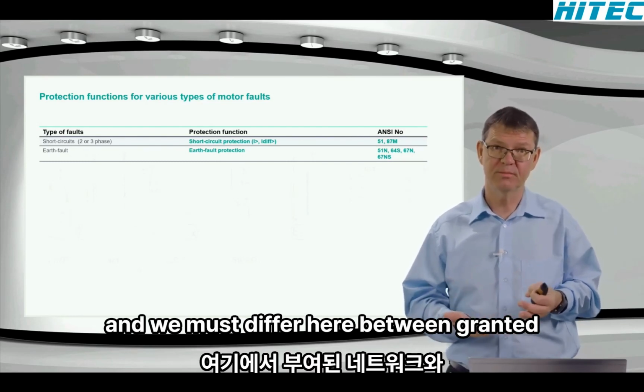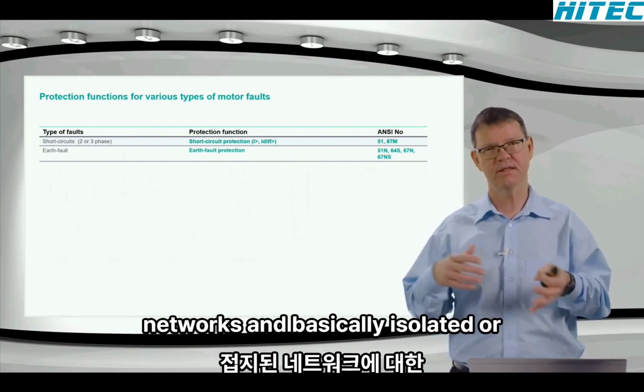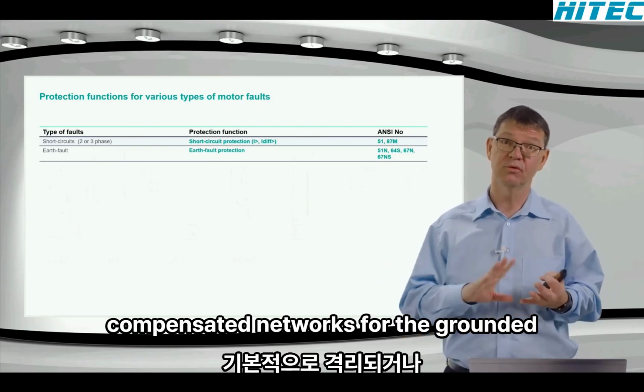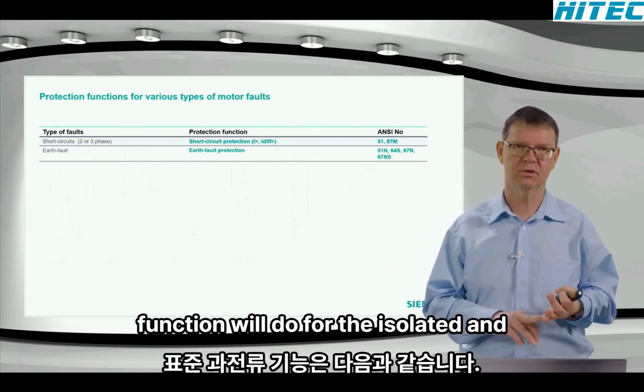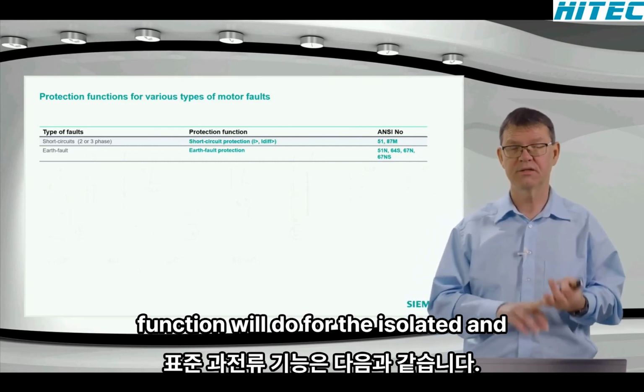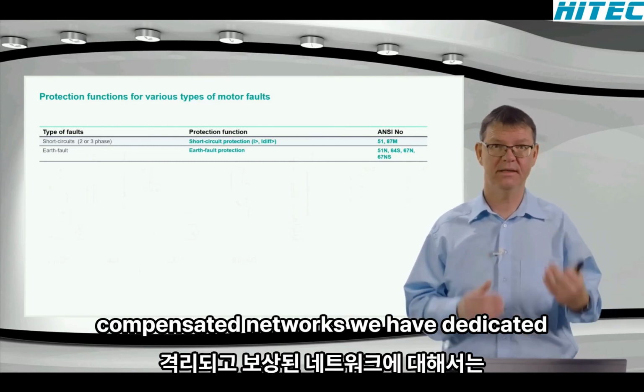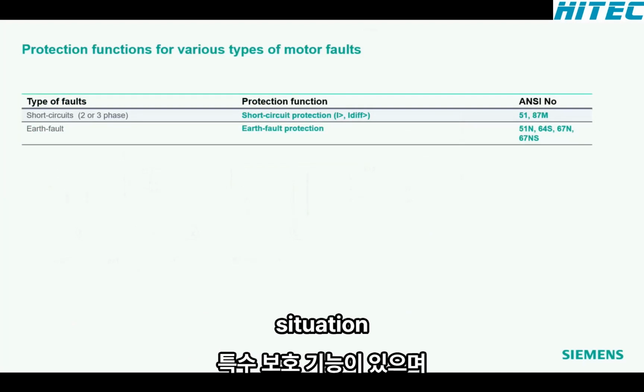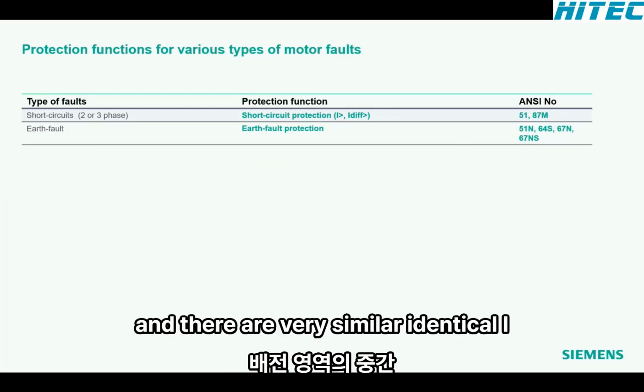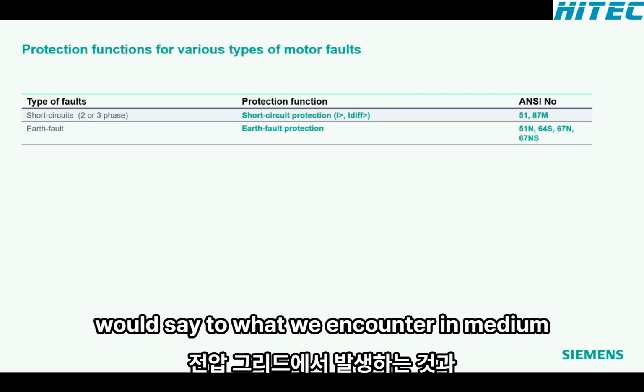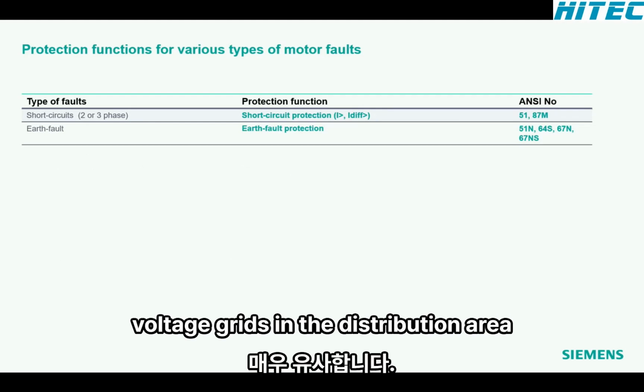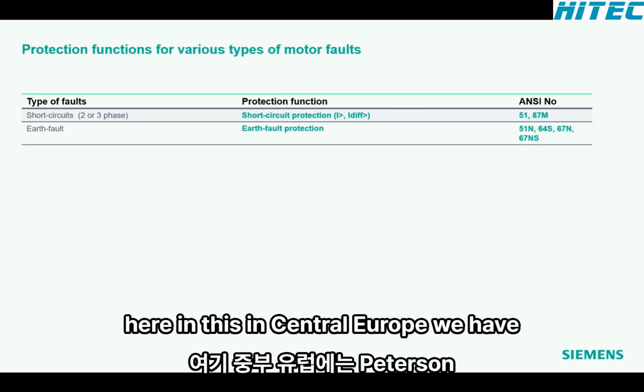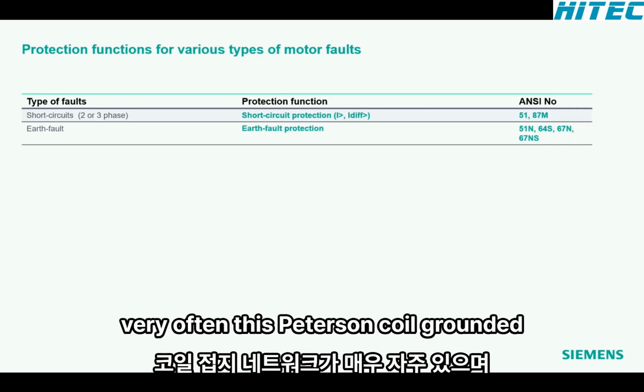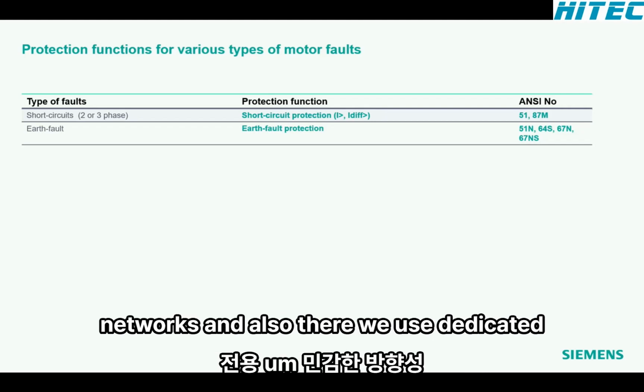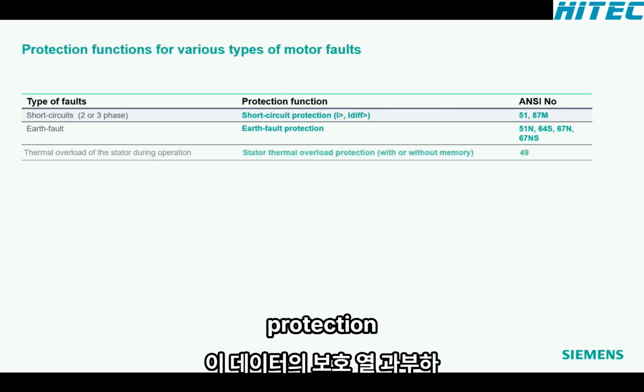And we must differ here between grounded networks and basically isolated or compensated networks. For the grounded networks, the standard overcurrent function will do. For the isolated and compensated networks, we have dedicated special protection functions for that situation. And they are very similar or identical, I would say, to what we encounter in medium voltage grids in the distribution area here in Central Europe. We have very often these Peterson coil grounded networks, and also there we use dedicated sensitive directional ground fault protection.